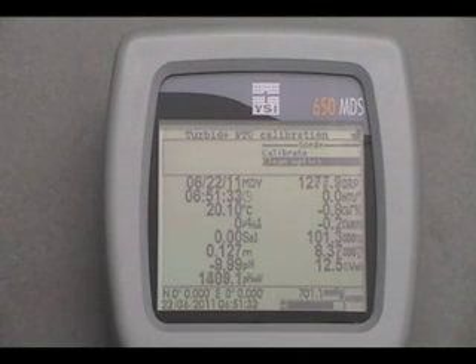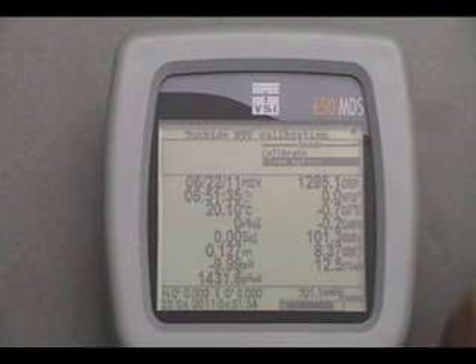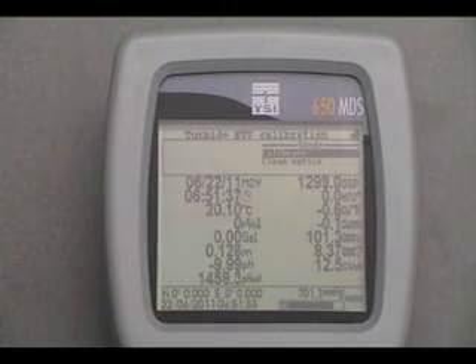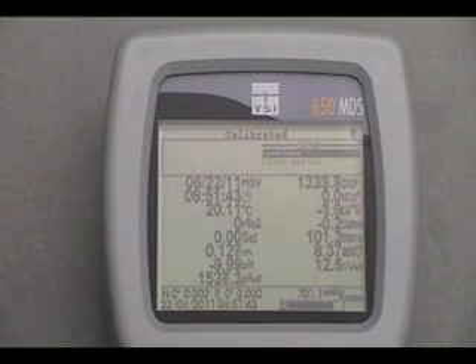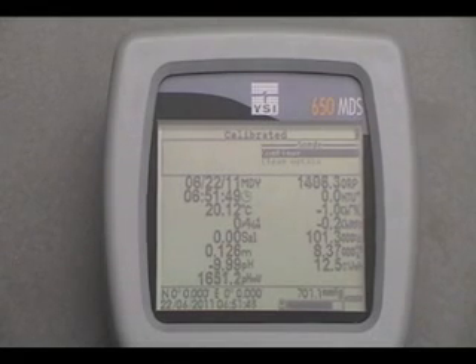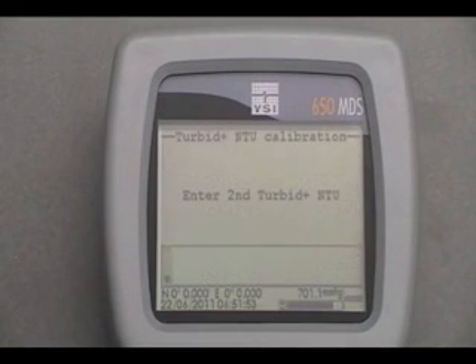Step 10. Highlight Calibrate and press Enter to confirm the first calibration. Record the post-calibration value for 0 NTU on the calibration worksheet. Step 11. Press Enter to continue. Step 12. Empty the cup and rinse the cup and sensors with DI water. Dry both the calibration cup and the turbidity sensor. Compressed air is handy for this step.